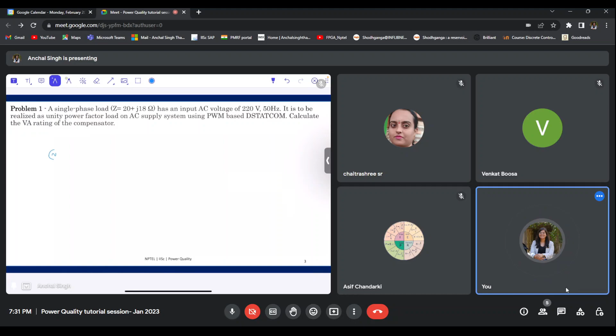So there is an AC source which is 220 volt 50 Hz, and then there is a load with magnitude 20 plus J18 ohms. Okay, and then we are connecting a compensator in shunt. Now we want the system to operate in unity power factor mode, and we want to find the VA rating of the compensator. Now we know that the voltage rating of the compensator is very clear. It is connected in parallel with the supply voltage. Will be 220 volts. Now we need to calculate the current rating of the compensator.